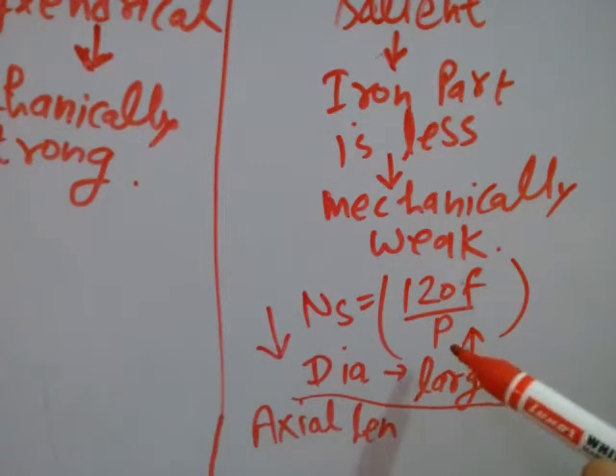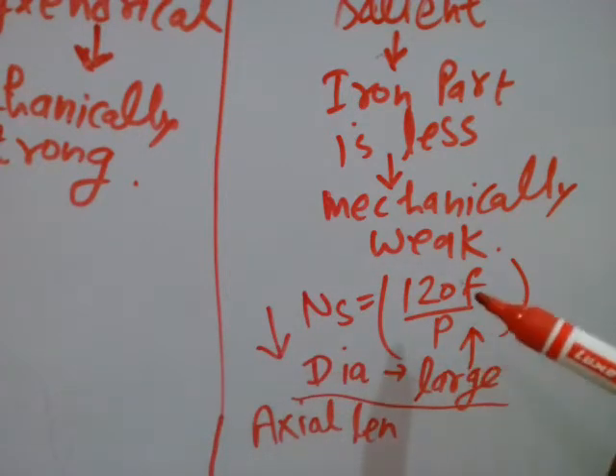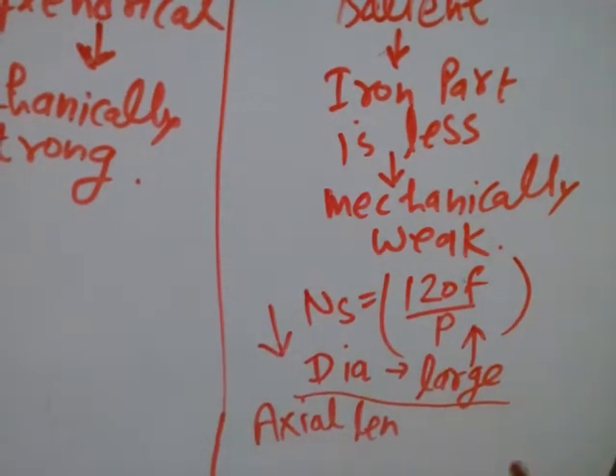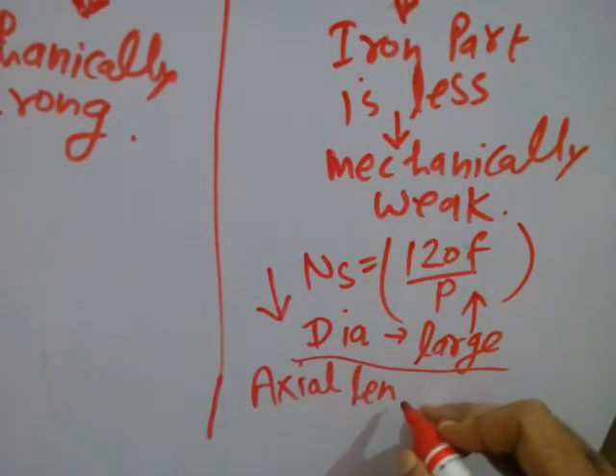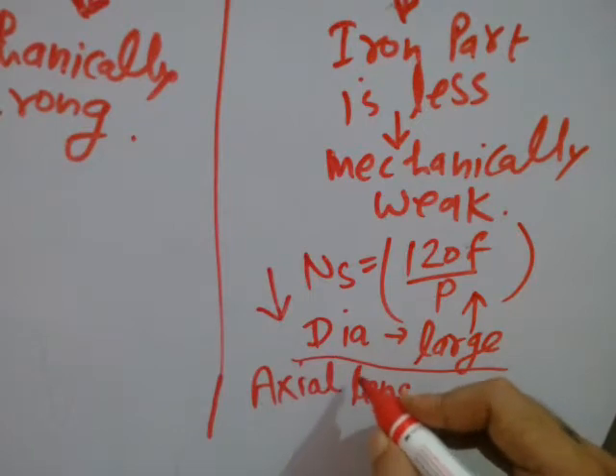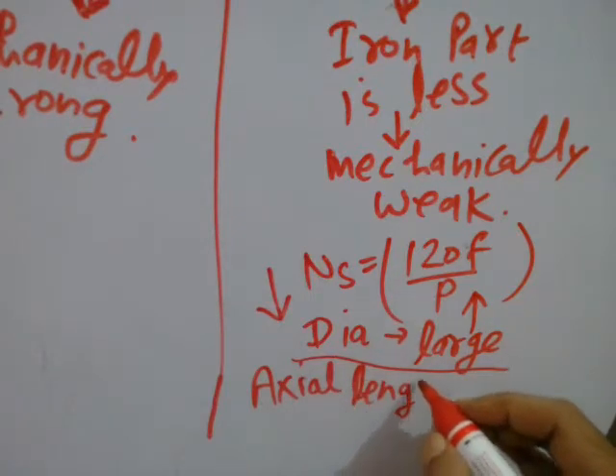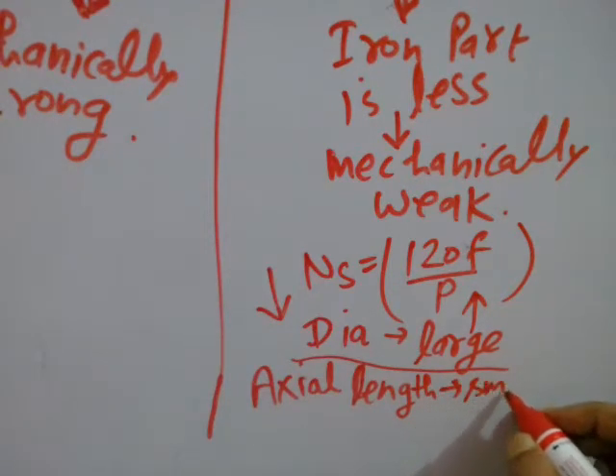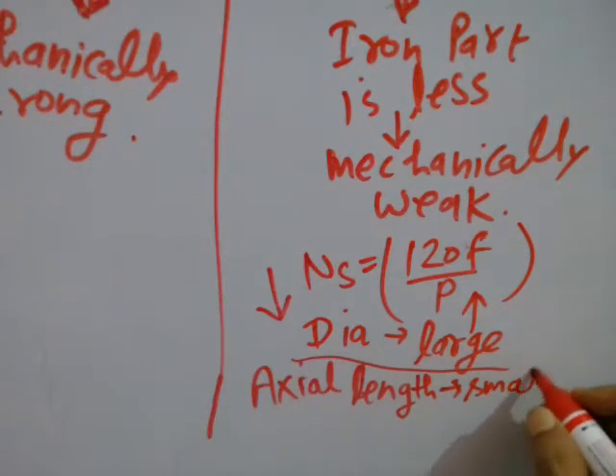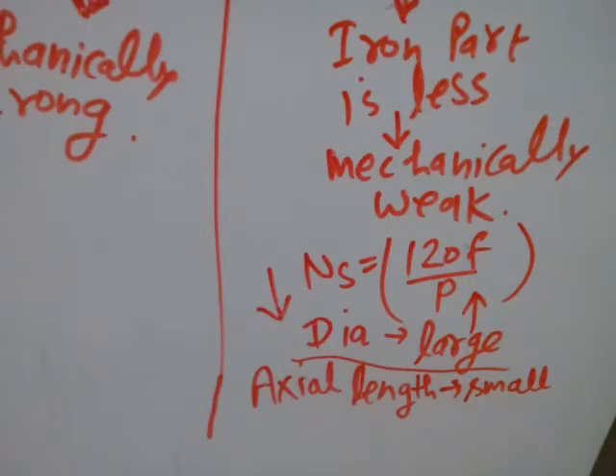If you want to fit a large number of poles on the periphery, then definitely the diameter will be large. If the diameter is large, that means the moment of inertia is large. To balance this large moment of inertia, the axial length must be small — as compared to the cylindrical rotor.